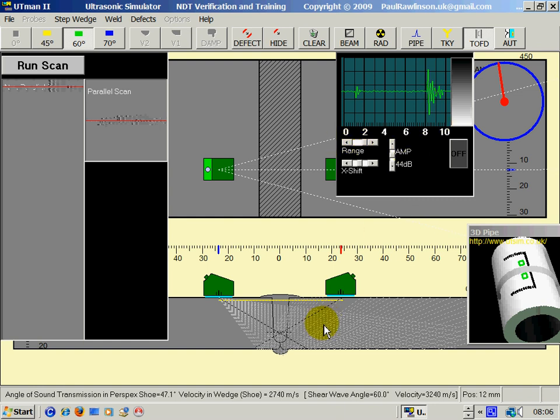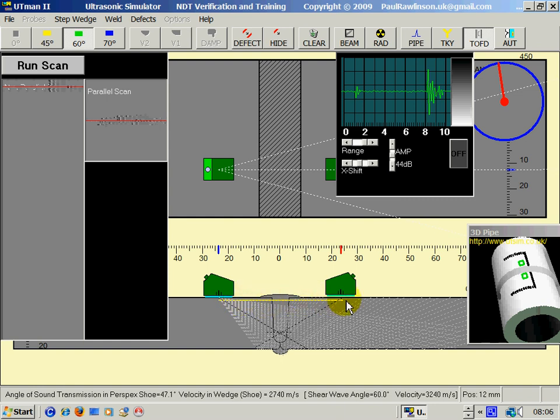Now the concept of TOFD, time of flight diffraction. That's what it stands for. The sound is transmitted and received here. But the edge of the beam actually runs just underneath the surface, shown by this yellow line here. As that is received, the first pulse is shown on the A-scan. Notice that it's an unrectified A-scan. The initial pulse here is actually called the lateral wave.